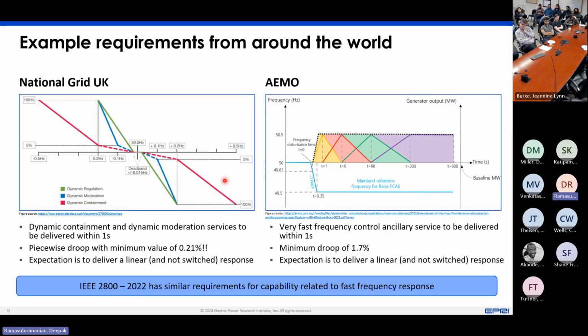So an example is some requirements around the world. If you take a look at some of the requirements in National Grid UK or AEMO, which is the Australian Electricity Market Operator, you would see some requirements like this. You have something called a dynamic containment and dynamic moderation service from an inverter-based resource, which is expected to be delivered within 1 second of initiation of an event. Of course, with some deadband settings and some droop settings. You have something similar from the Australian Electricity Market Operator, where they have something called very fast frequency control ancillary service, or very fast FCAS for short. And again, that needs to be delivered within 1 second, again with some droop settings.